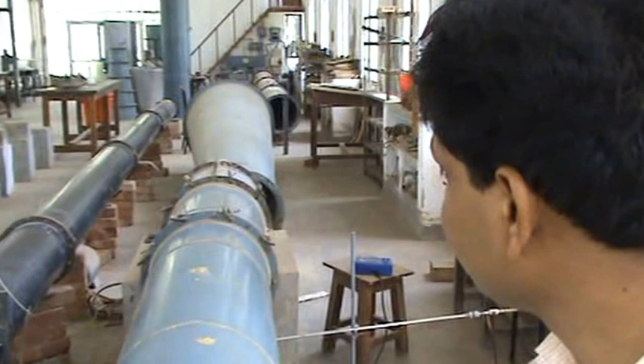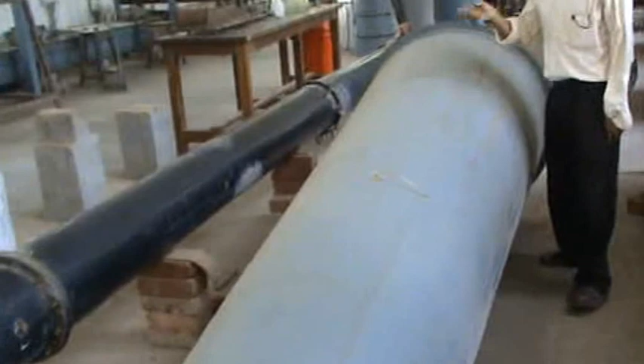So after this measurement, we will put a diffuser at the outlet of the fan, and this is the diffuser, and we will attach it here at the outlet of the fan, and with that diffuser we will also measure quantity and static pressure. Then from that we can find out how much the static pressure increased, and therefrom we also find out what is the efficiency, and also for that matter what is the quantity increment. With that, just after attaching the diffuser, we can find it out.